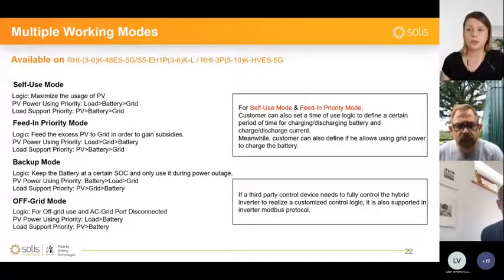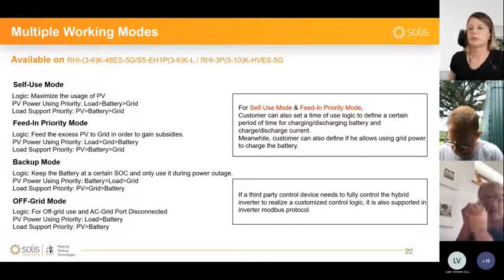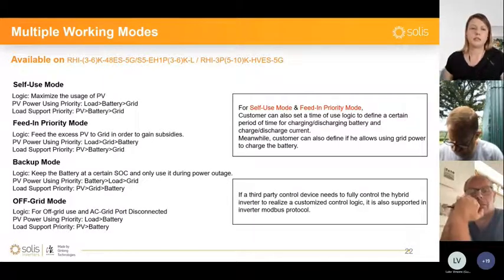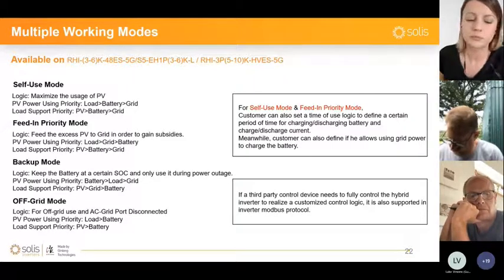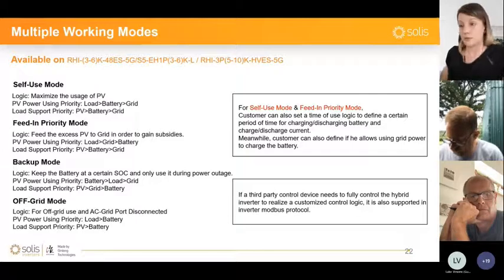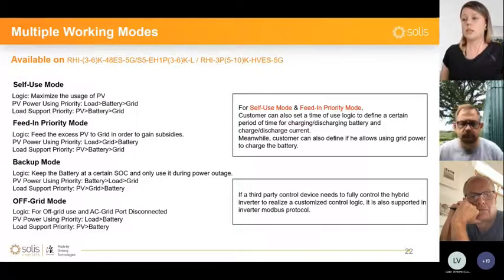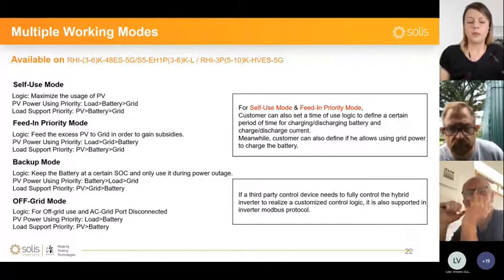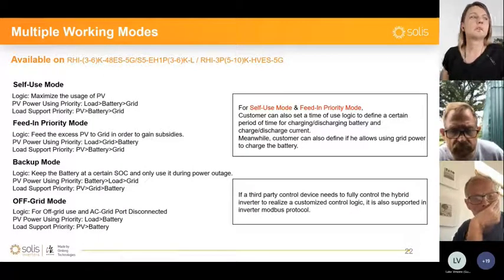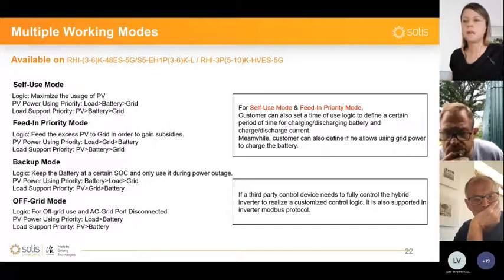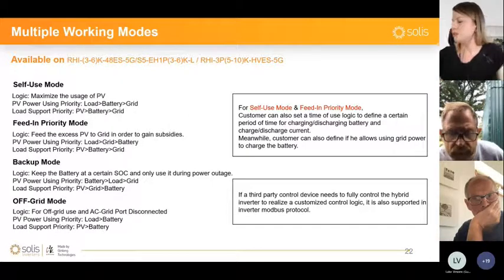And the fourth mode, sorry, is the off-grid mode. This is for remote locations where there is no grid available. The inverter is able to operate without having a connection to the mains, and it will only work with the PV and the battery, and it will feed power through the AC backup ports to the loads for that location.